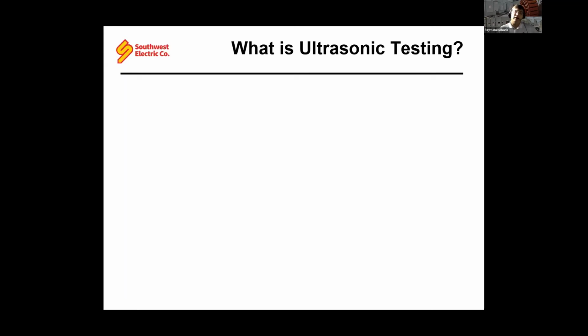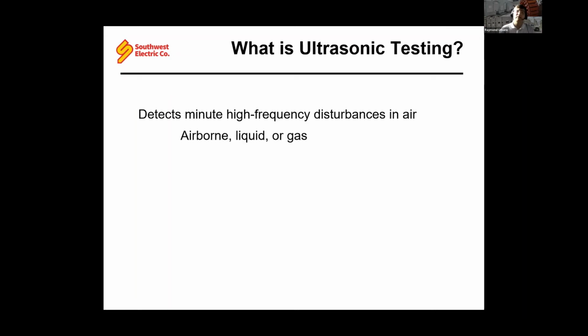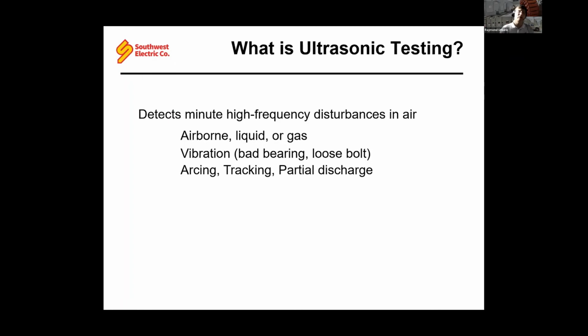So why ultrasonic testing? Well, it's a device that measures the disturbances in air, any kind of turbulence, and it measures its frequency, usually in the high frequency realm, well above 1,000 hertz. And this allows you to detect anything airborne, liquid, or gas, any kind of vibration like a loose bolt. And then it also does the electrical diagnostics of arcing, tracking, and partial discharge. And actually, each one of those has its own separate signature. We're going to look at that.